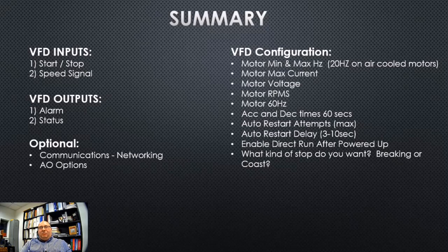When we talk about configuring the drive, on the left-hand side were physical input and output connections. When we configure the drive, it is then programmed in the menu system. We said earlier that the motor should have a minimum and maximum hertz, right? We should never go below 20 hertz, especially on air-cooled motors. The motor max current is the maximum amount of current programmed into the drive, so the drive doesn't let the motor go over that max current, or if it goes over, it can help throttle it down or shut itself off. The max current is going to be your run load amps times your service factor.